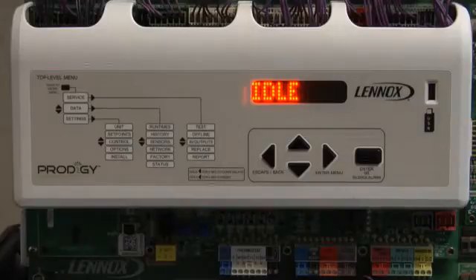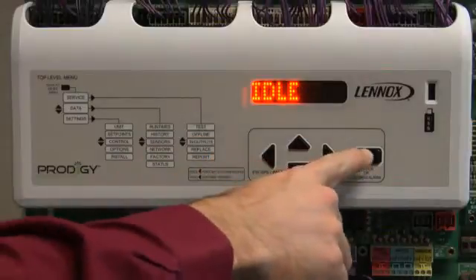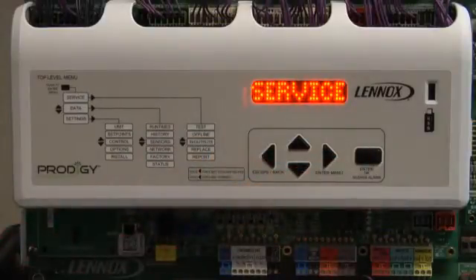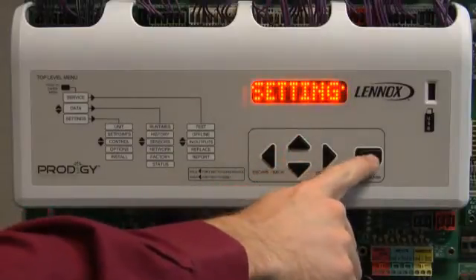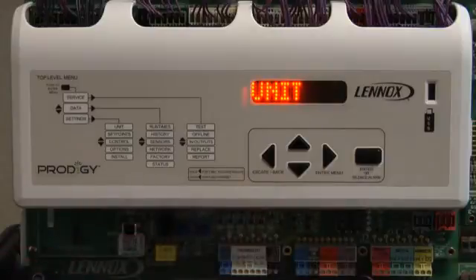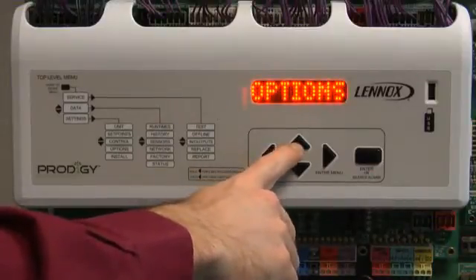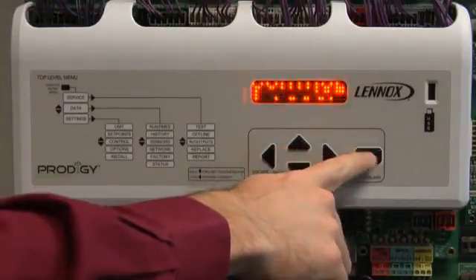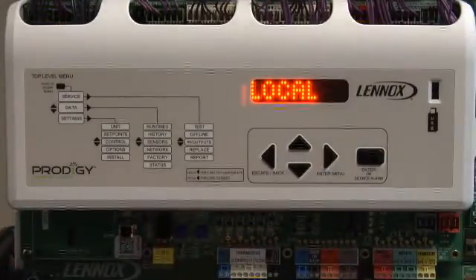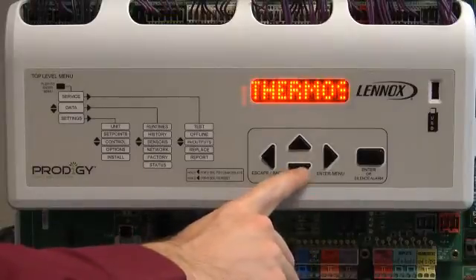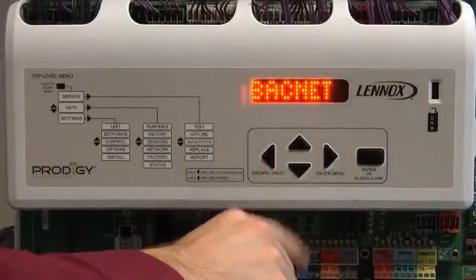Press enter until Service is displayed. Use the up or down arrow until Settings is displayed, then press enter. Unit will be displayed. Use the up or down arrow until Control is displayed, then press enter. Local will be displayed. Use the up or down arrow to navigate to BACnet, then press enter.